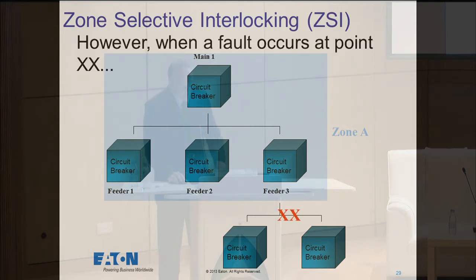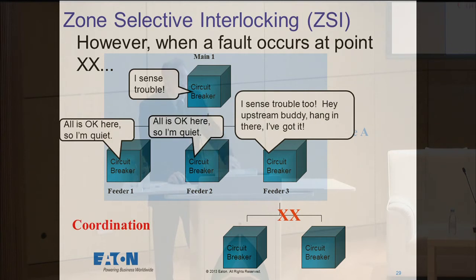So whenever a fault occurs further downstream, what happens? This guy senses trouble. These two on the left, they don't sense anything, but this guy says, hey, I sense it too. So now I have two breakers sensing it. And again, this was set up for coordination purposes, so he would normally wait a while and let this guy get it. This guy is telling him, I got it, don't worry about it. So he is picking it up, and then coordination is maintained, so only this one trips. So this is the background of how zone selective interlocking works, and now I'm going to show you what that means to arc flash.